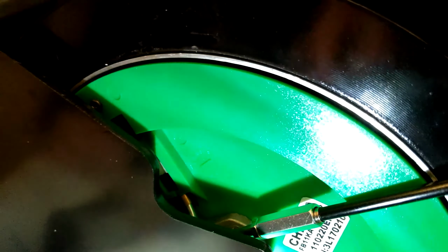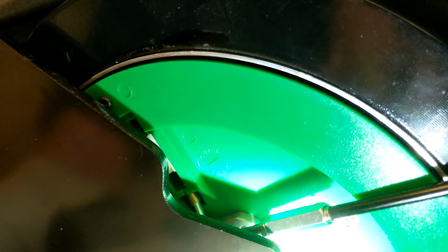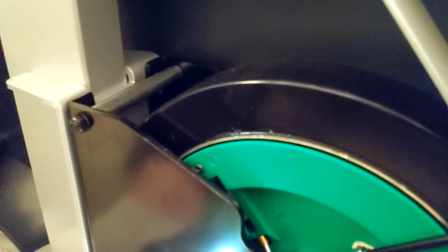What we can see here is it's not calibrated quite right. The white piece is a little too high - it's not within the 2 lines there on the green. So we're going to increase the tension on the cable to bring that down in between the 2 green lines.